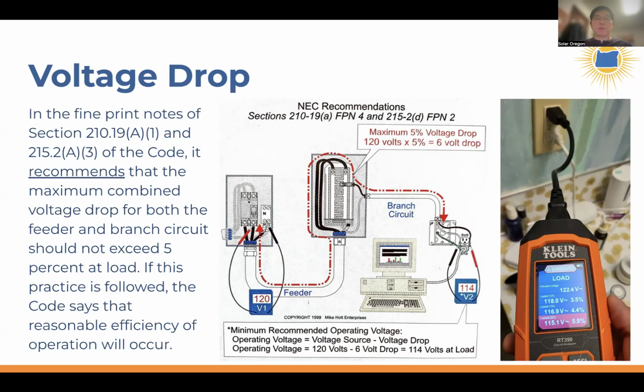Voltage drop is a function of bad connections between different daisy chains in a branch circuit, and also of very long branch circuit wiring. So, let's say you have 20 or 30 items daisy chained together, if you add up the length of the wire for that branch circuit, it'd be very long.